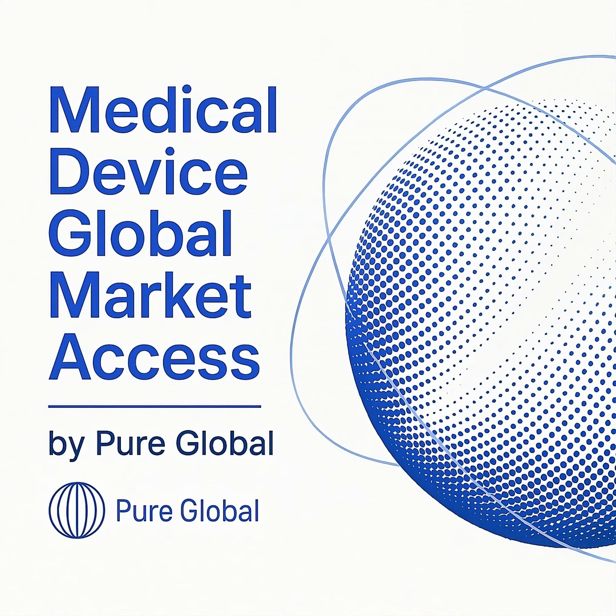Navigating the different submission formats is crucial. For the European market, a CE mark is obtained by compiling the technical documentation and, for most devices, having it reviewed by a notified body. The new MDR has significantly increased the level of scrutiny and clinical evidence required.